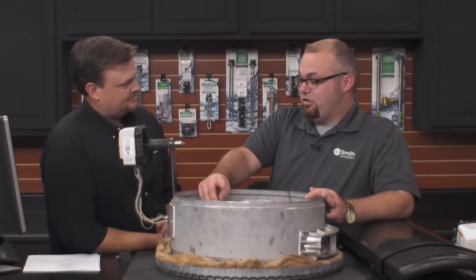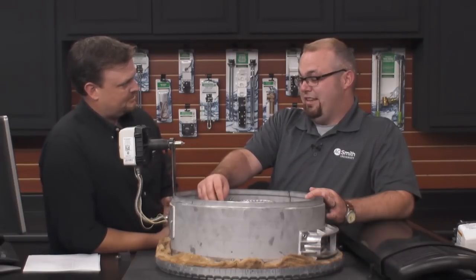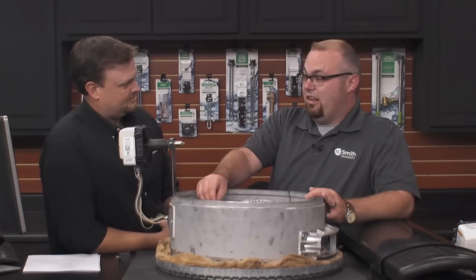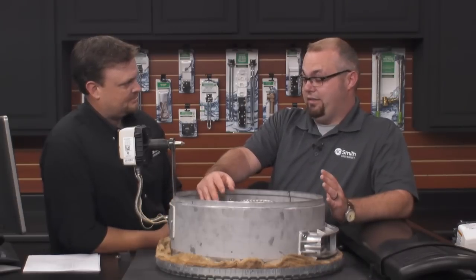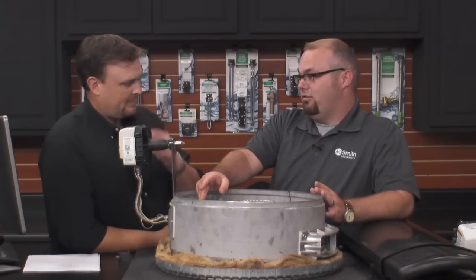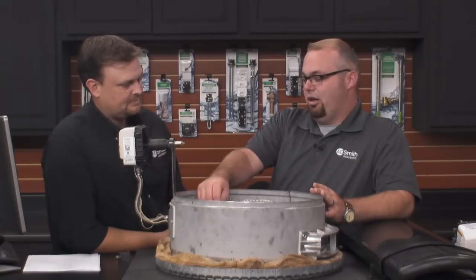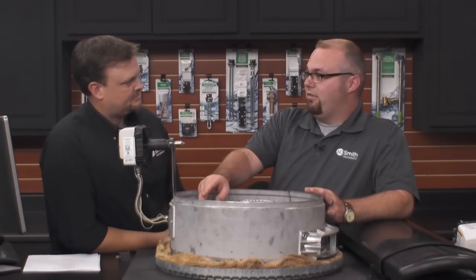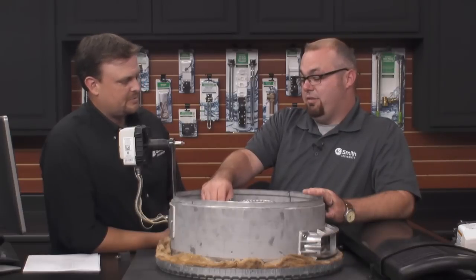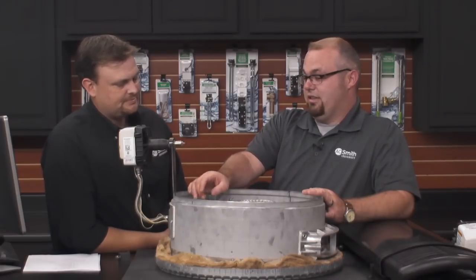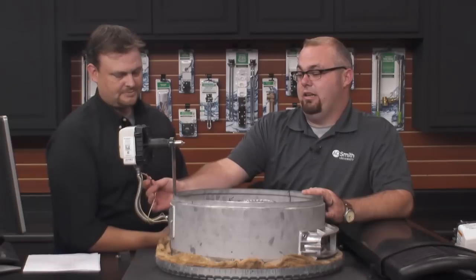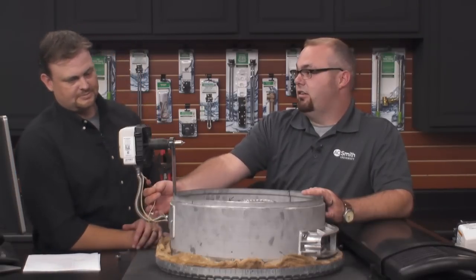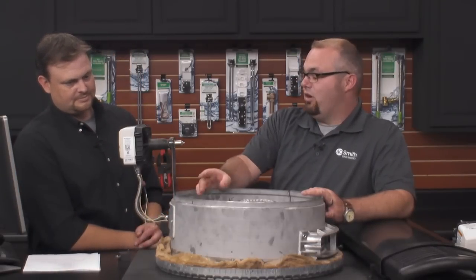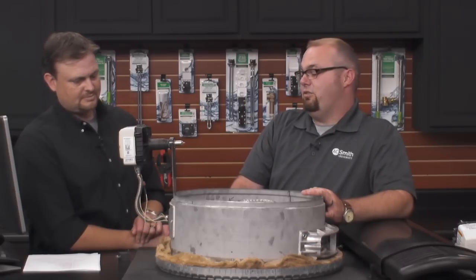But flame rods, you could clean it a lot, or say you accidentally damage it as you're cleaning it. You had to replace the whole igniter assembly on the older style water heaters, right? For just pretty much a cheap part, or a part that was a lot lower cost. Yeah. But with this, we can just change the flame rod, and it just connects to the hot surface igniter assembly with a flag connector. So it's pretty straightforward to replace it if you ever needed to.